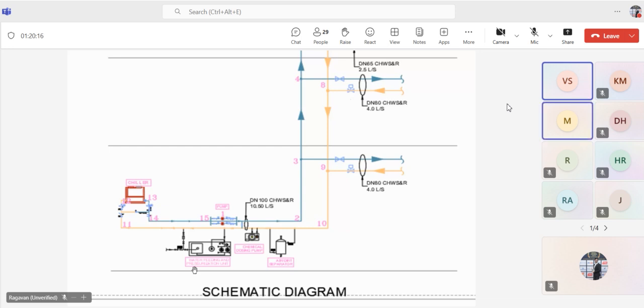Usually when you go for your own chiller, you go for an air cooled chiller, because with a water cooled chiller you need a cooling tower, which will take too much area. The air cooled and water cooled chillers also differ in price; water cooled is a little higher. So usually everybody prefers an air cooled chiller. But if you have a very big project, and you have the space, you can go for a water cooled chiller, no problem. If you have the budget also, you can go for a water cooled chiller.